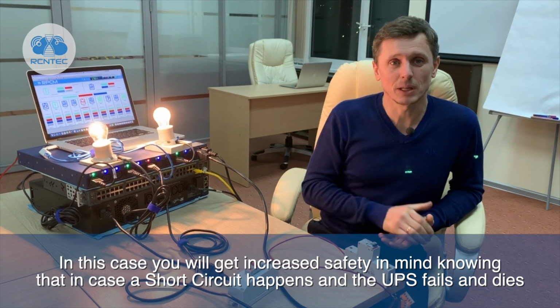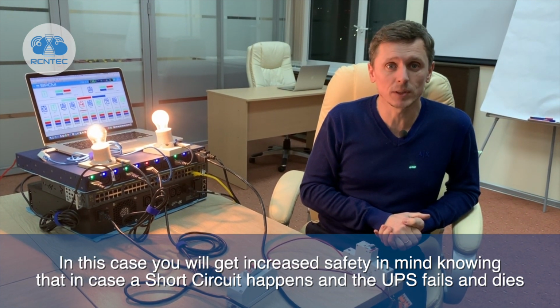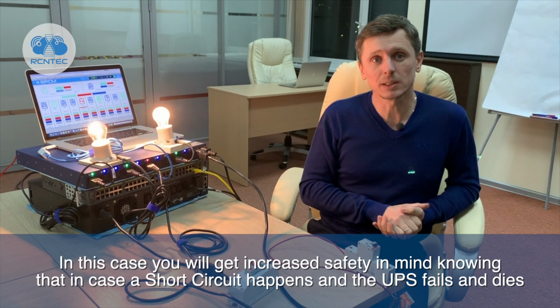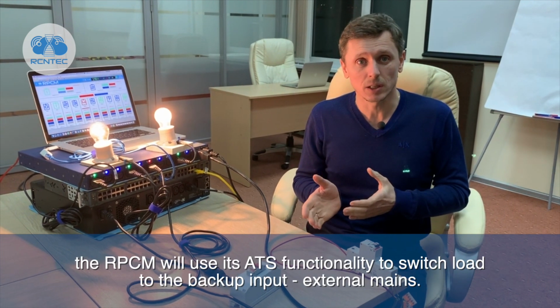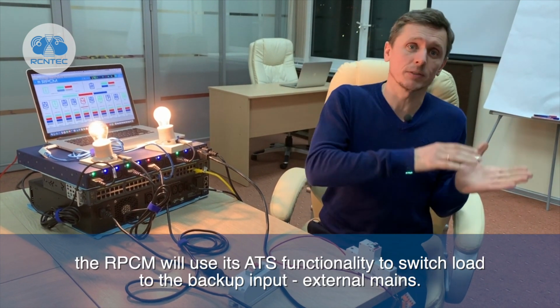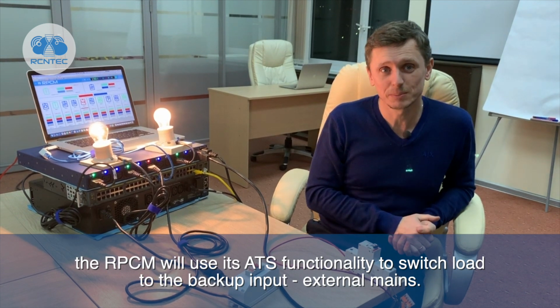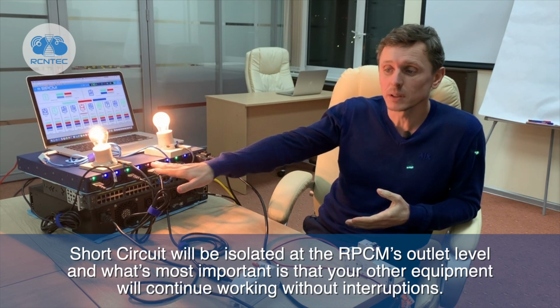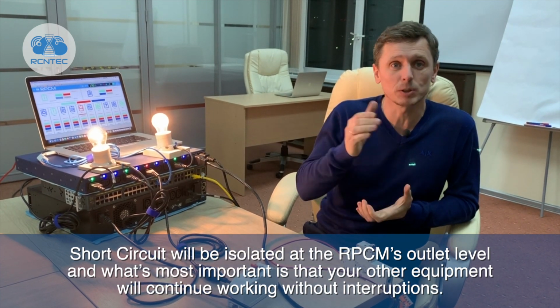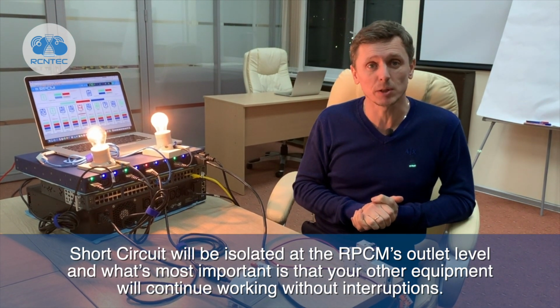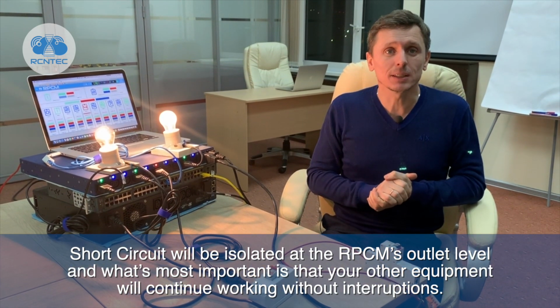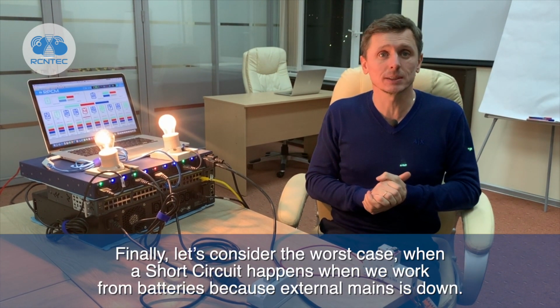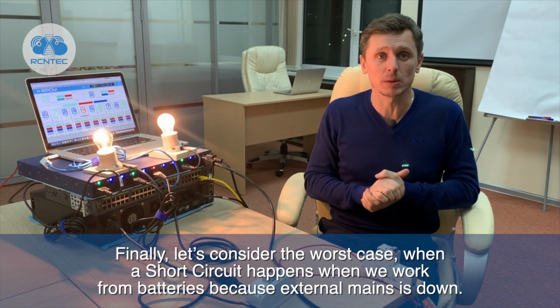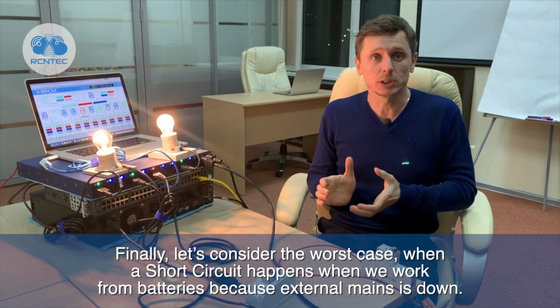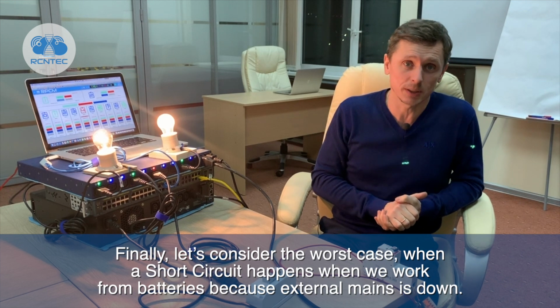In this case, you will get increased safety in mind, knowing that in case a short circuit happens and the UPS fails and dies, the RPCM will use its ATS functionality to switch load to the backup input, external mains. Short circuit will be isolated at the RPCM's outlet level, and what's most important is that your other equipment will continue working without interruptions. Finally, let's consider the worst case, when a short circuit happens when we work from batteries because external mains is down.